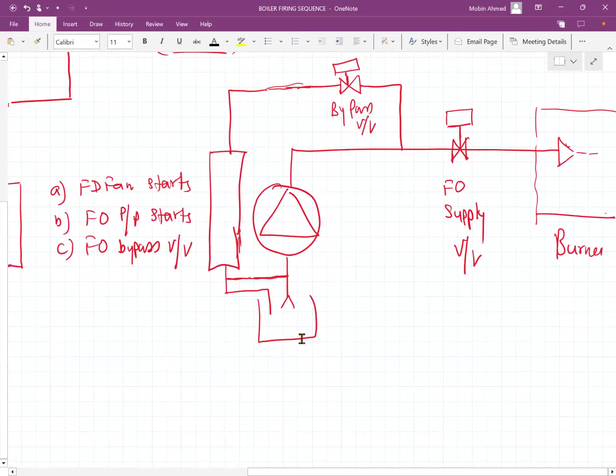The FO supply valve will remain closed. Your air damper opens fully. The reason for this is to expel the flammable gases of the furnace. That is the pre-purging. So pre-purging is going to start and continue for at least a set time. Some systems have 3 minutes, and in some systems it is 5 minutes. If the time is completed, yes, then it will go to the next. If no, it will continue.